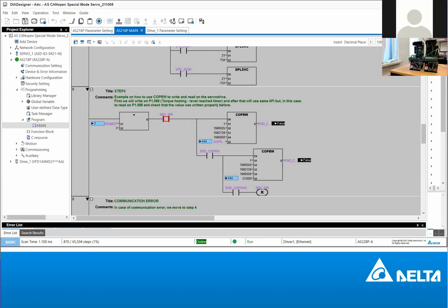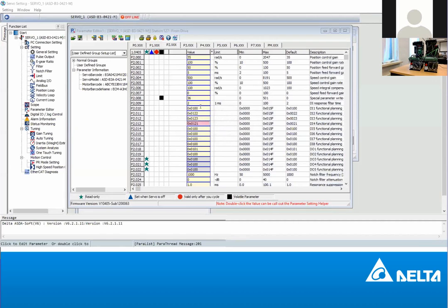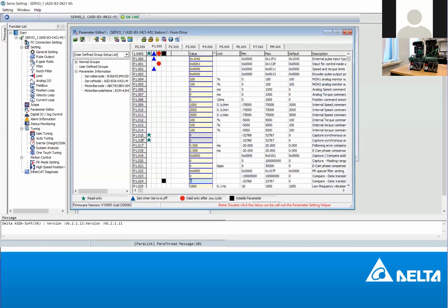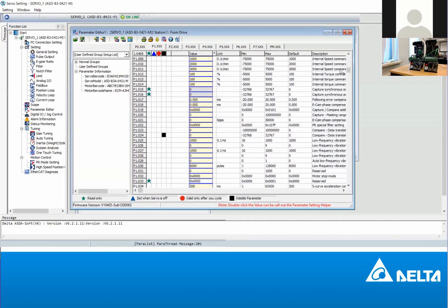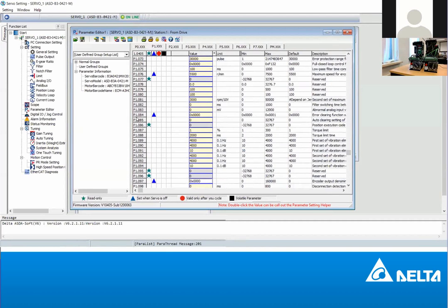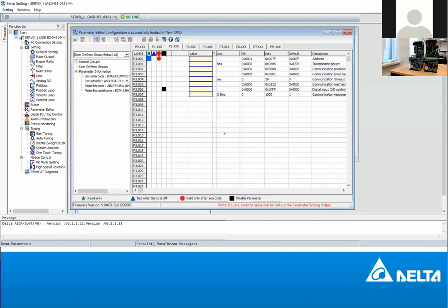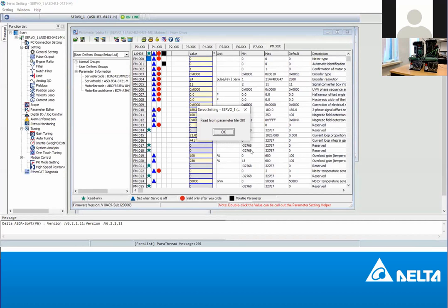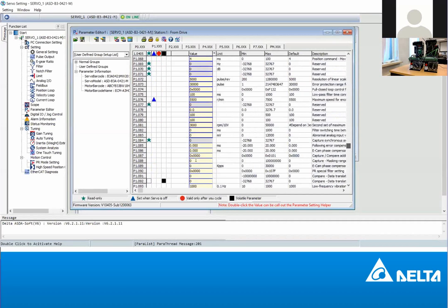And the same thing also, if our parameter editor is connected, the same should also apply. If I read the parameter, I go online, you should see 444, parameter 188. If you scroll down to 88, index 88, 88 is down below. Parameter 188. So let us read. If we read the drive parameter, it should give us 444. Parameter read is okay. Parameter 1, let's go back again, 88. What do we have? Perfect. We have 444. You see how easy it is to send command to your parameter register using this API.